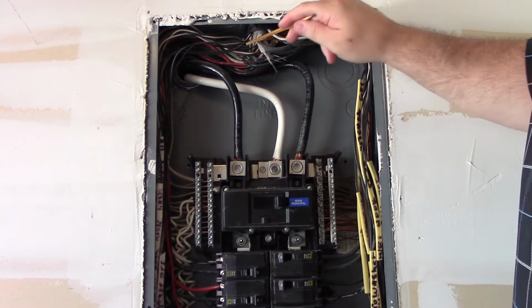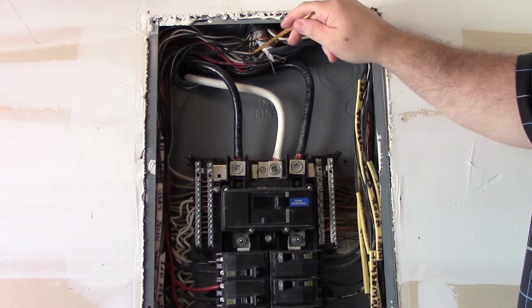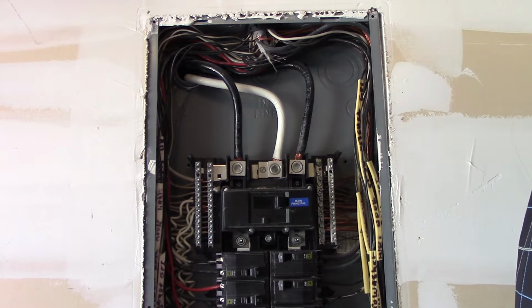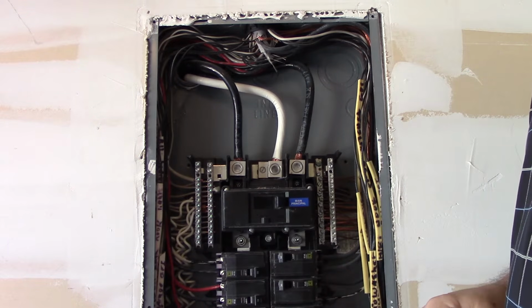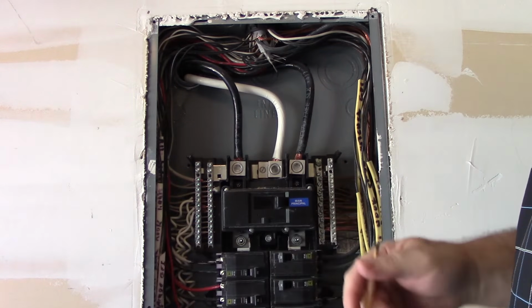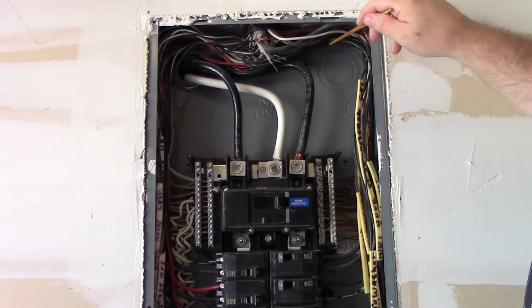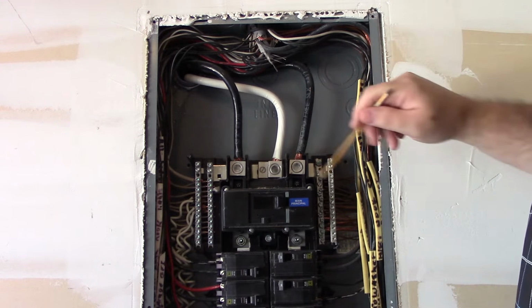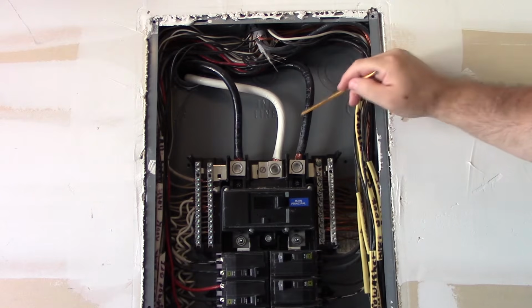Okay, but this might be acceptable in your jurisdiction. They might have allowed something like this. Again, the National Electrical Code does not permit this application. All right, it does with an exception, but not in this case. All right, so I'm looking at all these conductors and everything looks good. So I get down to these conductors here.